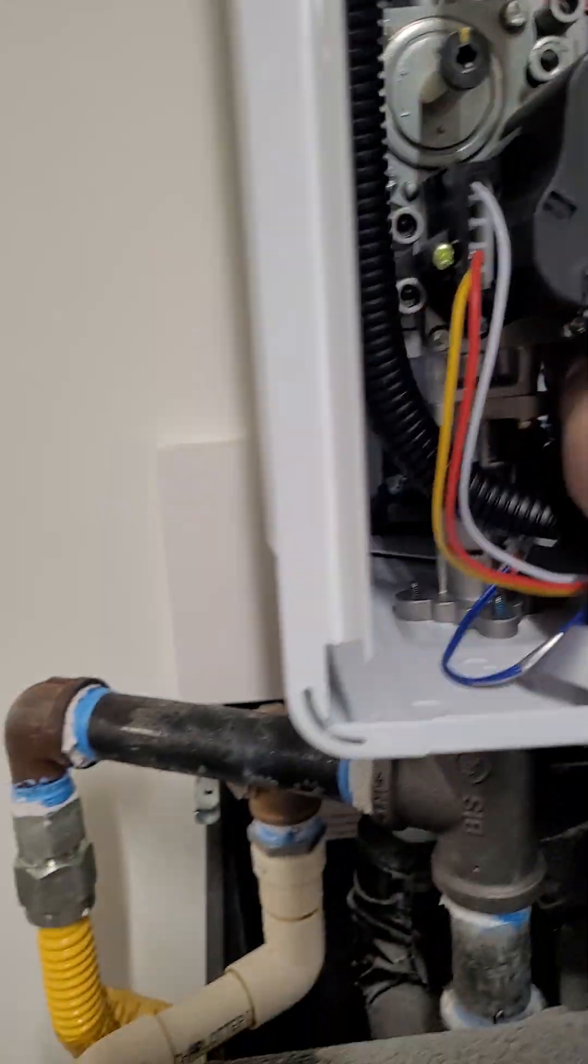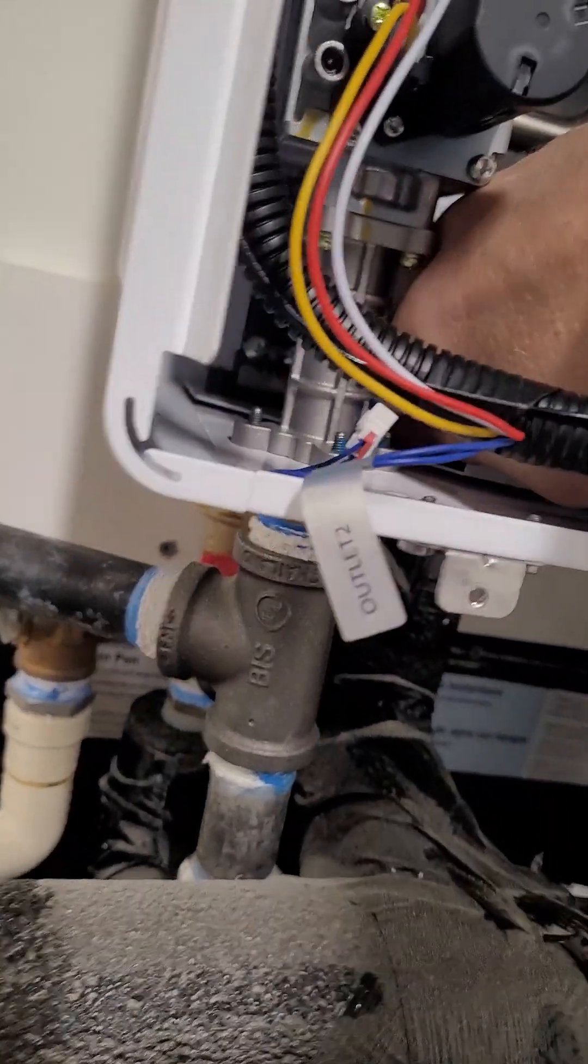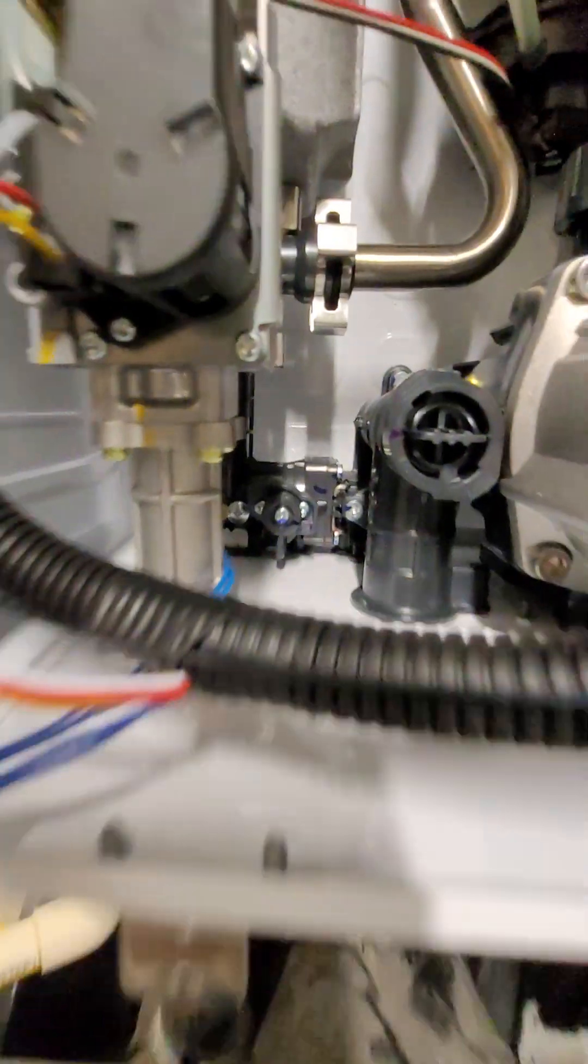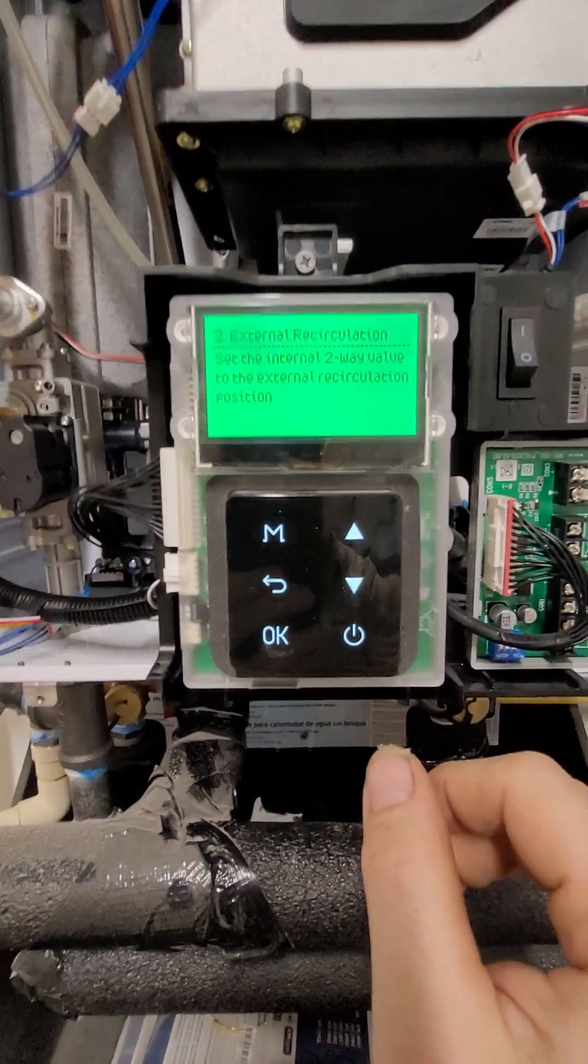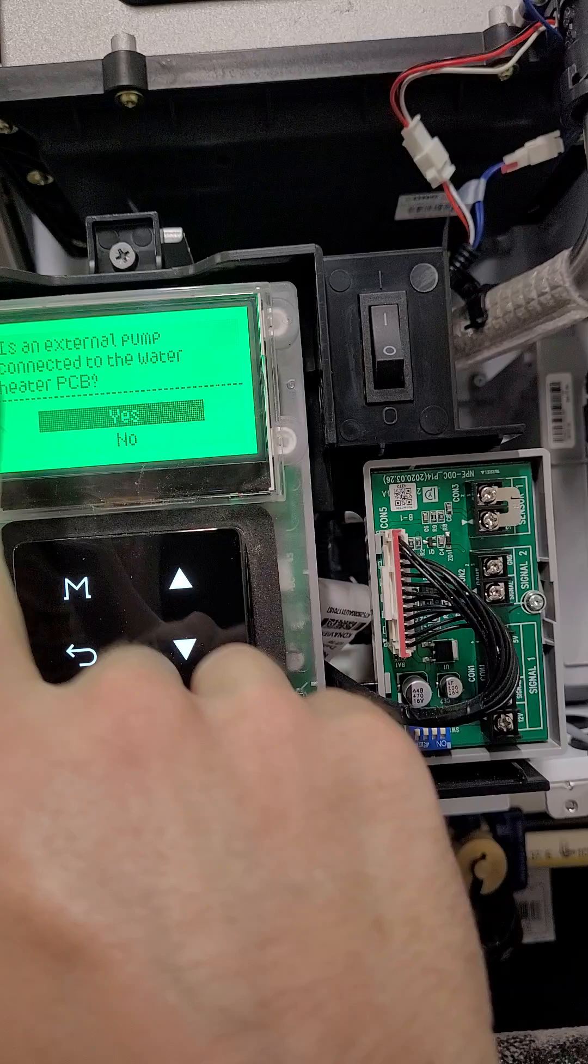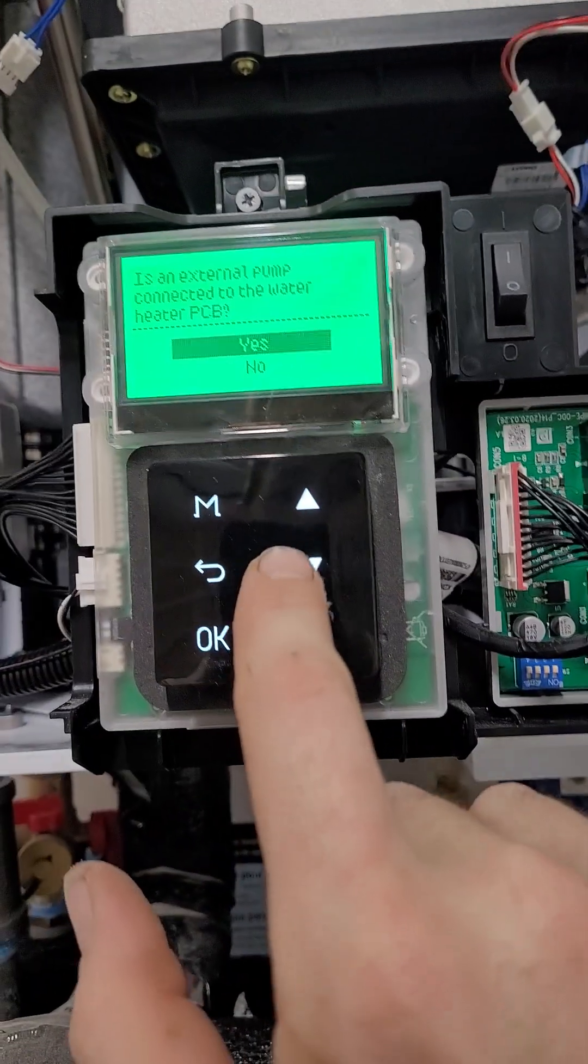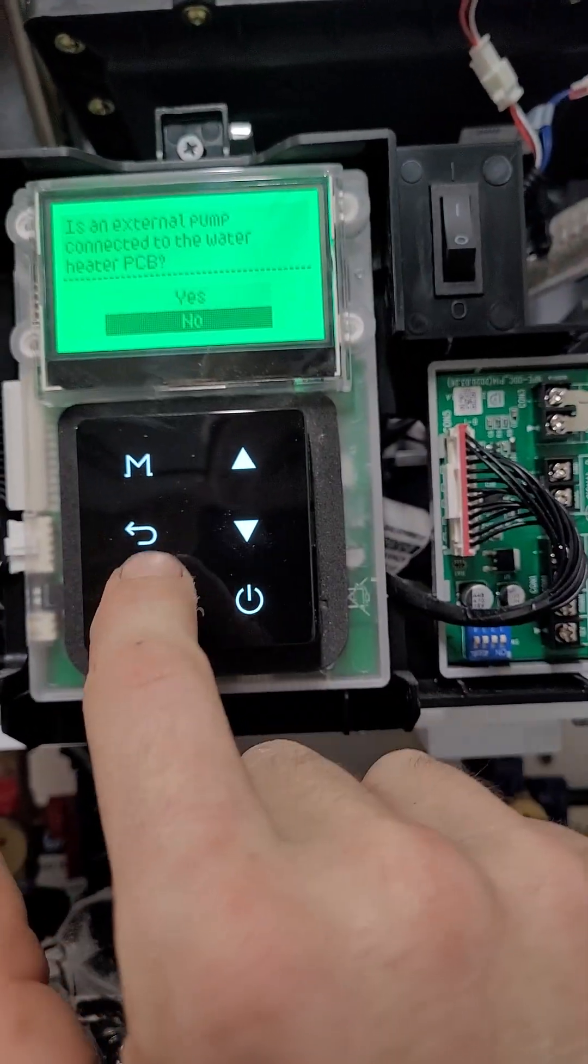It's going to tell us to change this thing back here in the back. We're going to reach all the way down here and give it a quarter turn into the down position. As you can see, that'll say external right there on the bottom right. Then we're going to hit the okay button again. Get my camera back. Is there an external pump connected to the water heater? Primary control board? No. There's no pump out here.